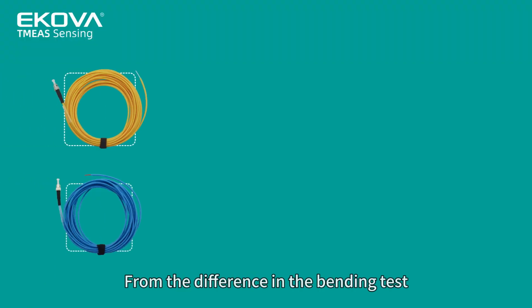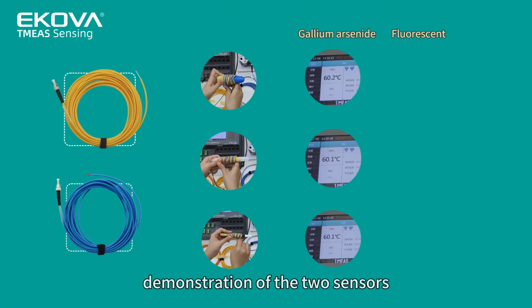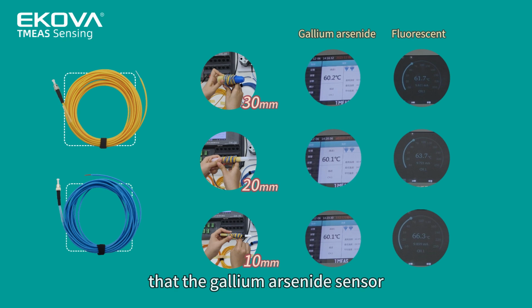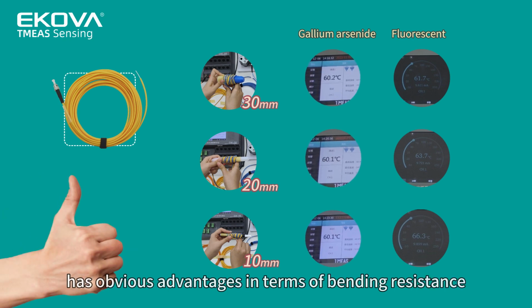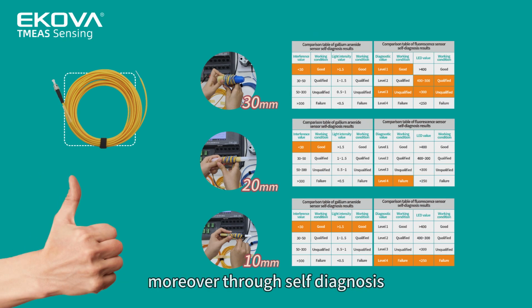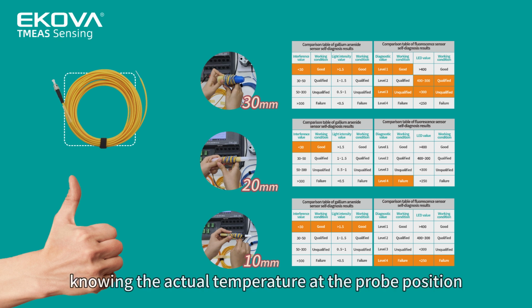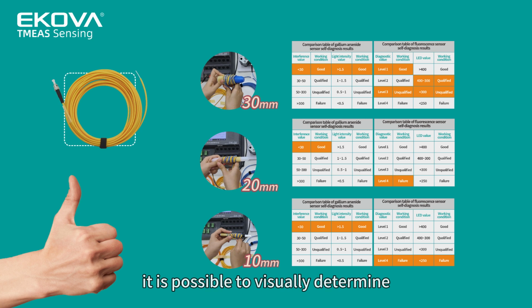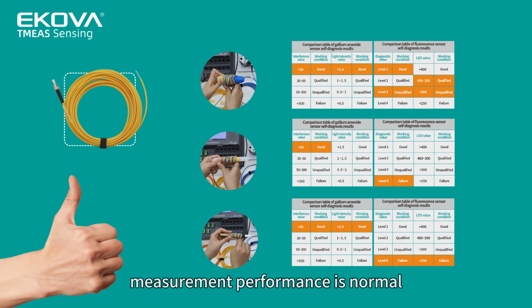From the difference in the bending test demonstration of the 2 sensors, we can intuitively see that the gallium arsenide sensor has obvious advantages in terms of bending resistance. Moreover, through self-diagnosis, even without knowing the actual temperature at the probe position, it is possible to visually determine whether the temperature measurement performance is normal.